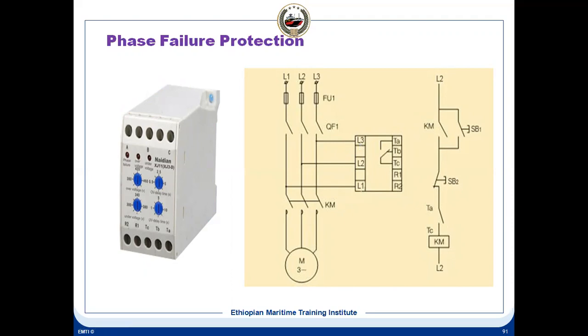So whenever in a three-phase supply one of the phases goes, L1, L2, L3, suppose let's say the L1 phase has gone. In this case, what happened? You see here, there's a relay inside, with TC, TA and TB. This relay will operate, and it is connected in the same series circuit as the main contactor KM. So suppose one of the phase failures takes place, this TA relay will open and trip the motor. So this is called phase failure.